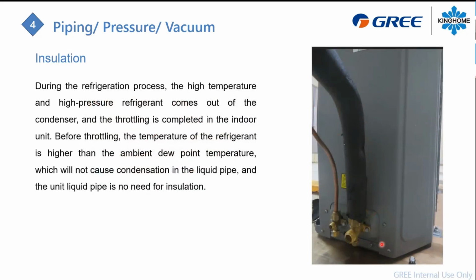On the outdoor valve here, on this picture, this is an example of a 5-ton unit. For this kind of unit, the valve is outside, and the 3/8 is not insulated, and you will push your Armaflex as far as you can go on the valve here. At a certain point, yes, this valve may condensate, but it's a normal thing when you are in cooling, and this valve is outdoor.